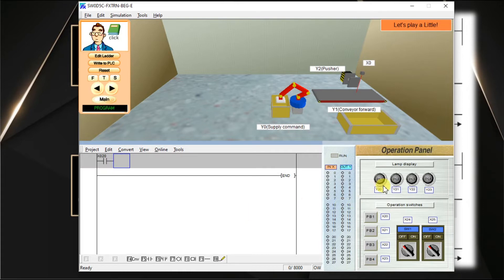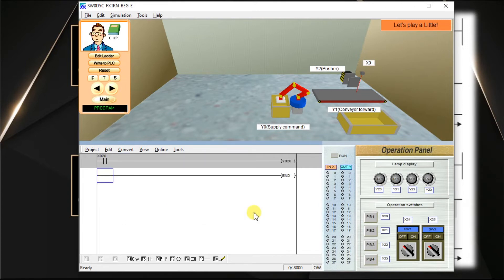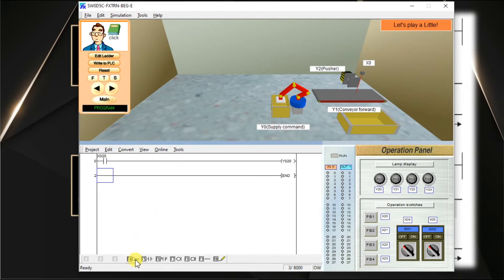I want to use output lamp 1. For output instructions, we have to add a coil. Click on the coil symbol. The address of lamp 1 is Y20 — enter Y20 and click OK. Now I have created a simple logic for the normally open contact. I am going to download this logic into the PLC. First we have to compile it — click Convert. The grey background color is removed, which means the program is successfully compiled without any error.